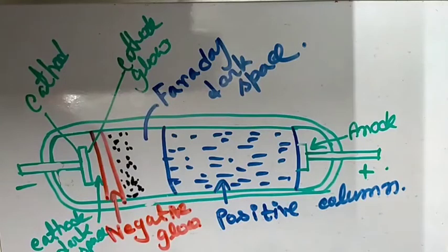And in order to reduce power loss at the cathode, a long lamp is required, which in turn necessitates a higher operating voltage for these lamps. And the bombardment of the cathode also causes its gradual disintegration with consequent blackening of the tube, and there is a tendency for cleanup of the gas, with the result of a reduction in the life of the lamp. Next, we discuss the sodium vapor lamp.